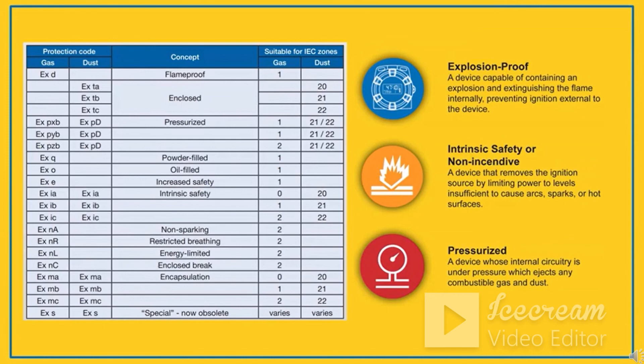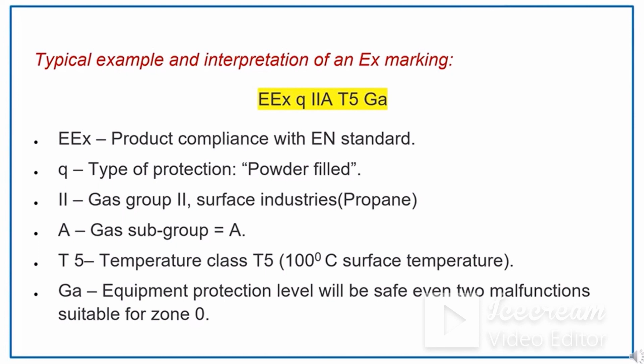Now we will take an example of explosion proof marking. Here the explosion proof marking is highlighted in yellow. The first term is EEX, which is a product compliant with EN standards. Q is the type of protection, which is powder filled. 2A is the gas group, which means propane gas. T5 is the surface temperature class, which is 100 degrees Celsius. Ga is the very high equipment protection level, safe even after 2 malfunctions, and suitable for zone 0 applications.